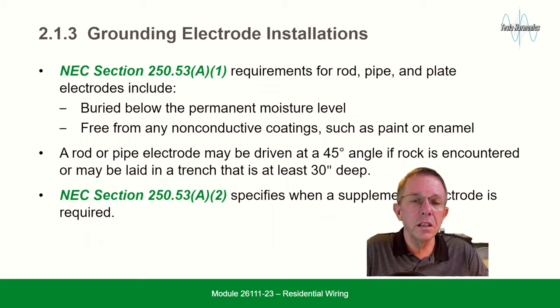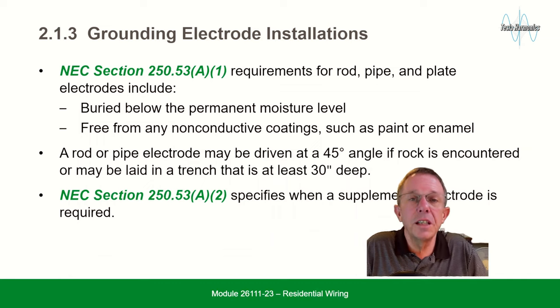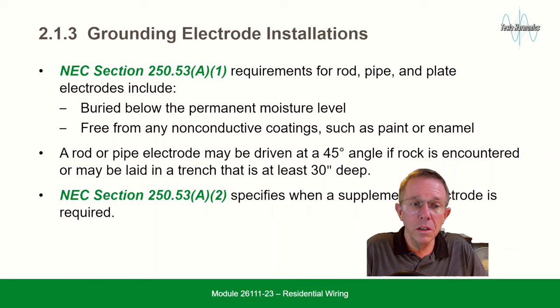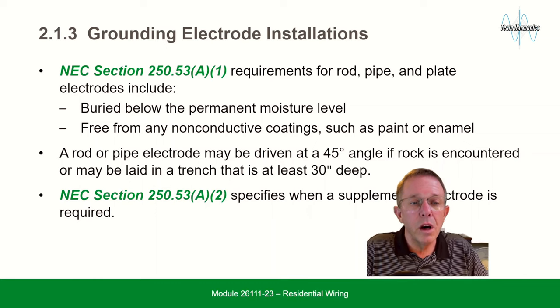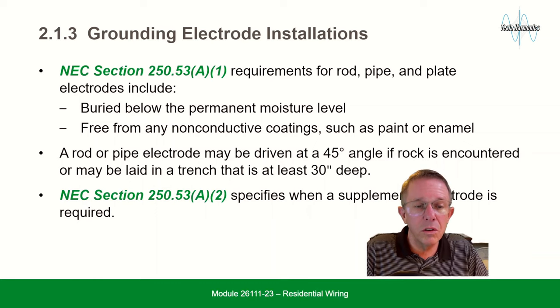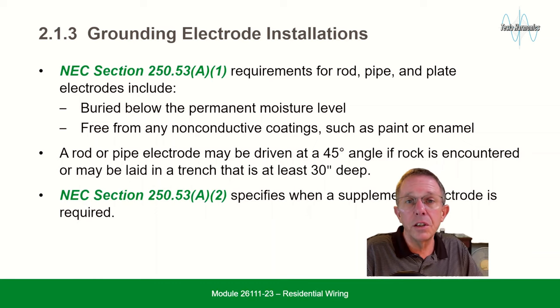Grounding electrode installations: NEC section 250.53 requirements for rod, pipe, and plate electrodes include being buried below the permanent moisture level and free from any non-conductive coatings such as paint or enamel. A rod or pipe electrode may be driven at a 45-degree angle if rock is encountered, or it may be laid in a trench that is at least 30 inches deep.